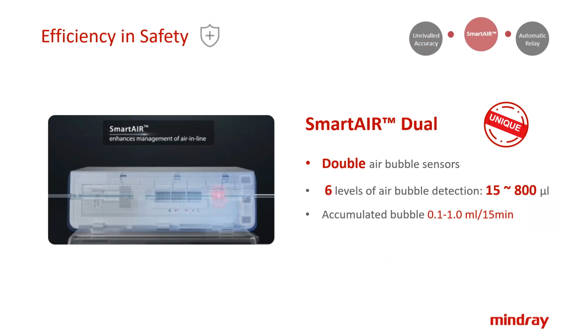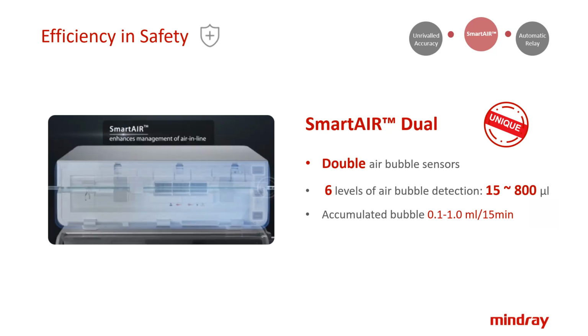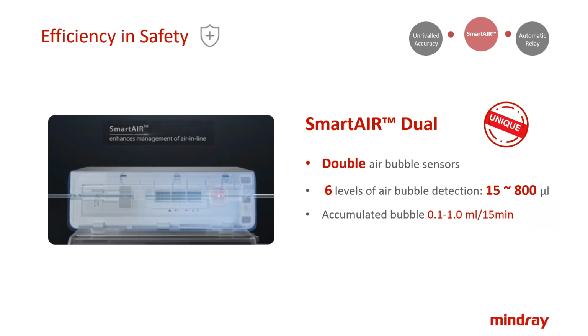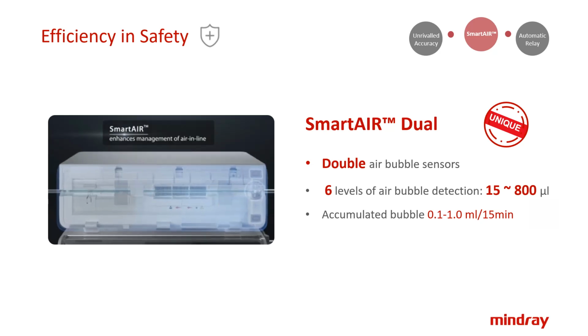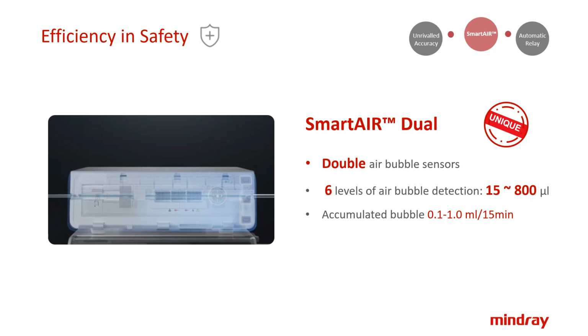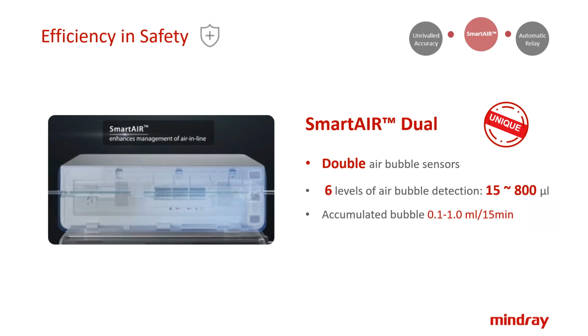Then let's go to the smart air dual functions. On the EVV pump, we have 2 air bubble sensors to detect the air bubbles. By those sensors, we can detect the air bubble very quickly and very easily. So we can support up to 6 levels of the air bubble detection from 15 to 800 microliters, and the accumulated bubbles from 0.1 to 1 milliliter per 15 minutes. So this function is also unique on our E-series pump.